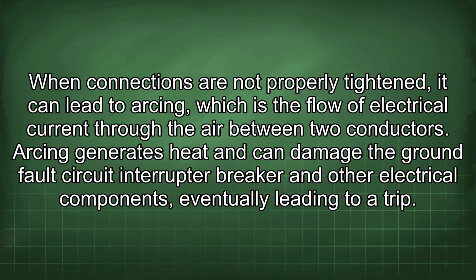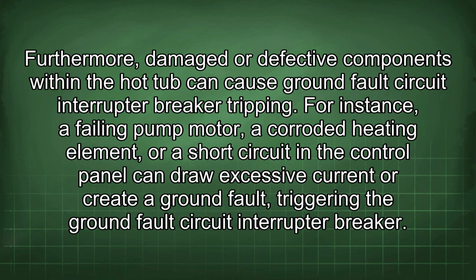Loose electrical connections can also cause ground fault circuit interrupter breakers to trip. When connections are not properly tightened, it can lead to arcing, which is the flow of electrical current through the air between two conductors. Arcing generates heat and can damage the ground fault circuit interrupter breaker and other electrical components, eventually leading to a trip. Furthermore, damaged or defective components within the hot tub can cause ground fault circuit interrupter breaker tripping. For instance, a failing pump motor, a corroded heating element, or a short circuit in the control panel can draw excessive current or create a ground fault, triggering the ground fault circuit interrupter breaker.